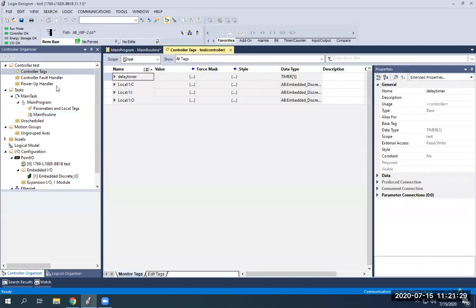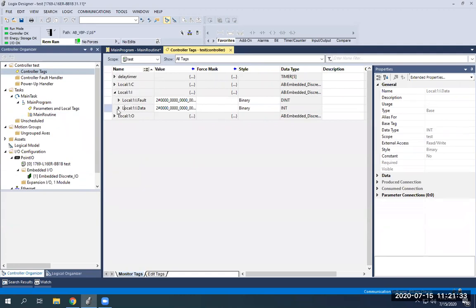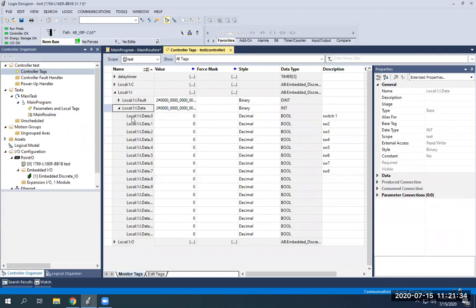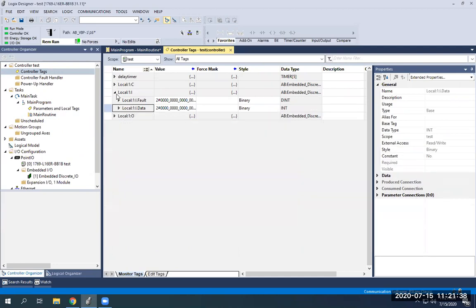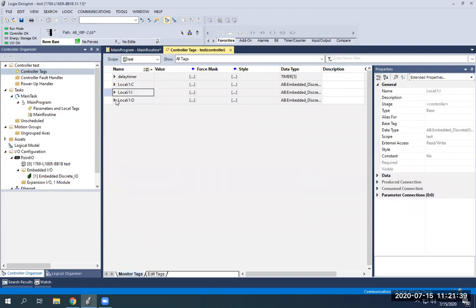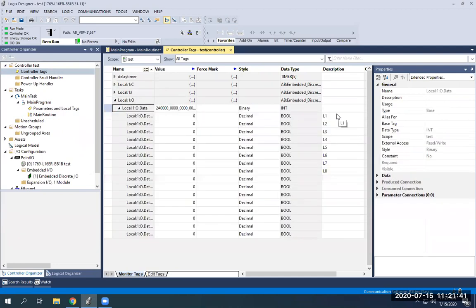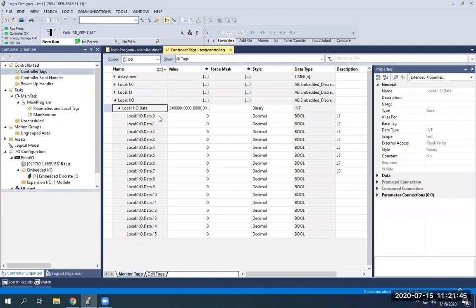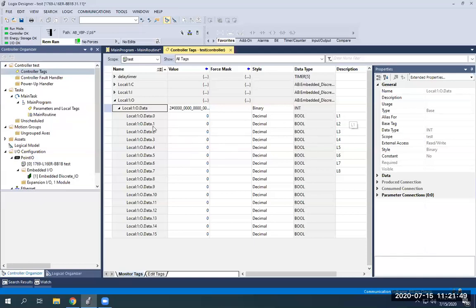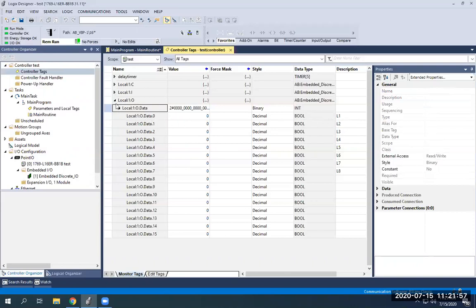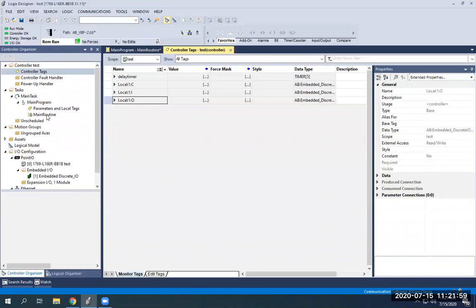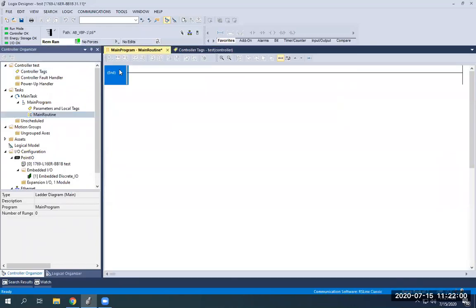Let's pull that up real quick. Under local 1 inputs, under data, we have switch 1 through switch 8, which will be data 0 through 7. And then our local 1 outputs, we have light 1 through light 8, which is associated with addresses 0 through 7. So remember, you give these a description based on what they are. Just by giving a description, that does not make it what it is. It's already got an address. You're just giving it the description.